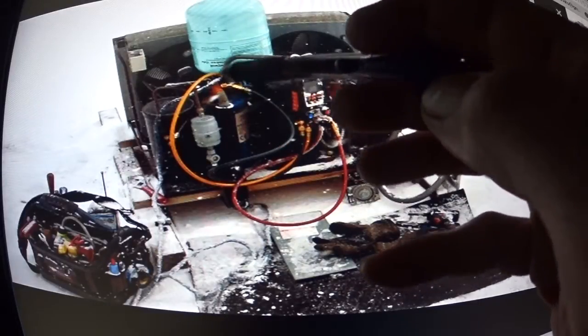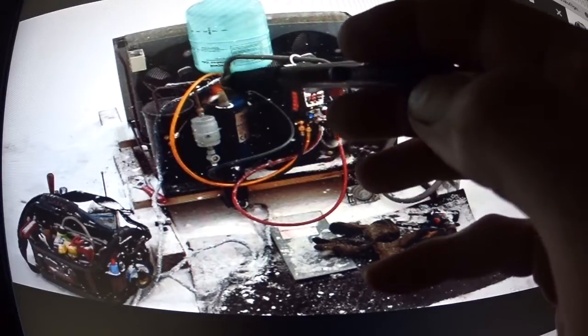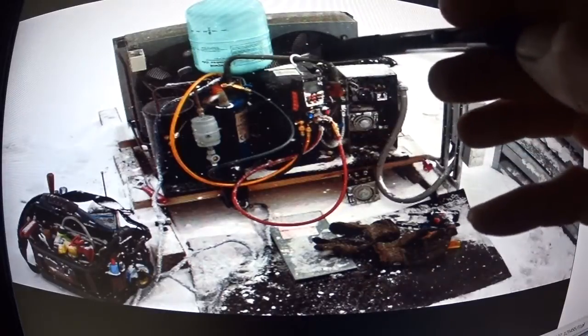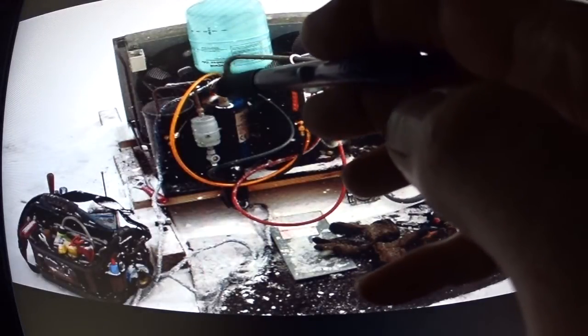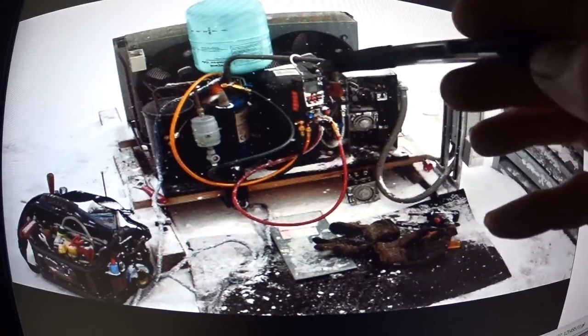I hooked up my hose and put a Schrader valve before the suction accumulator so I could put liquid into the system. Rather than putting liquid directly into the compressor, I can charge it faster — I put liquid in, it boils off, and I get gas going into the compressor.